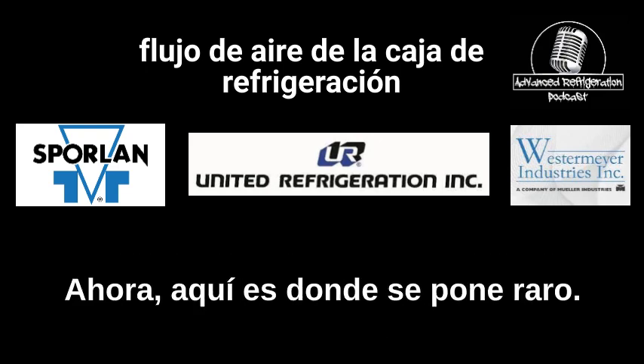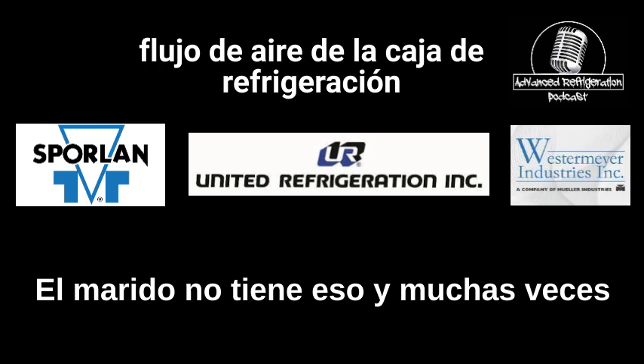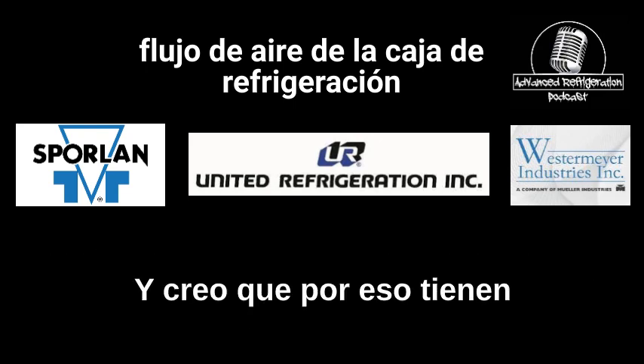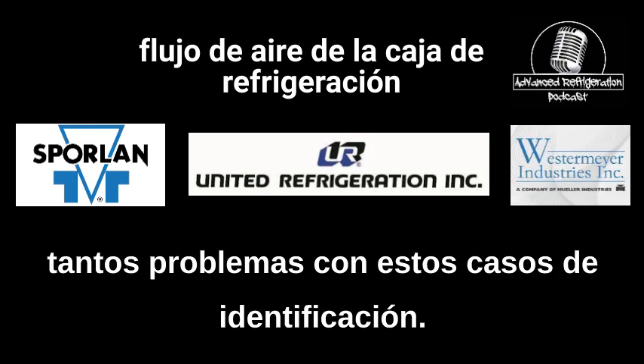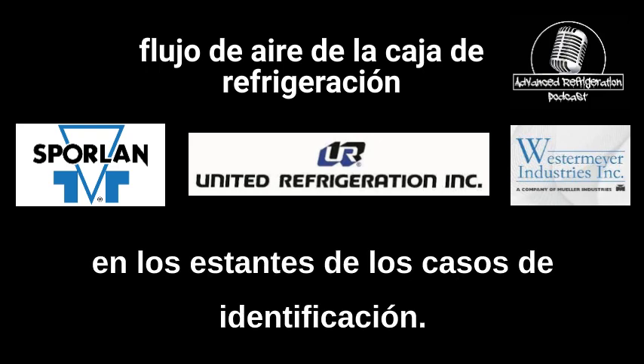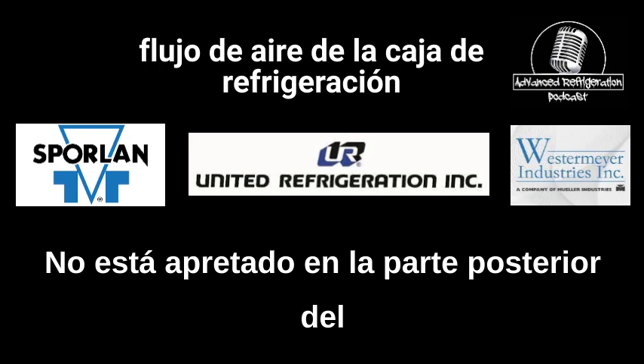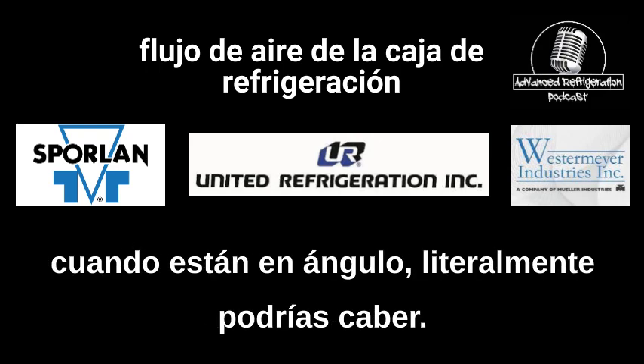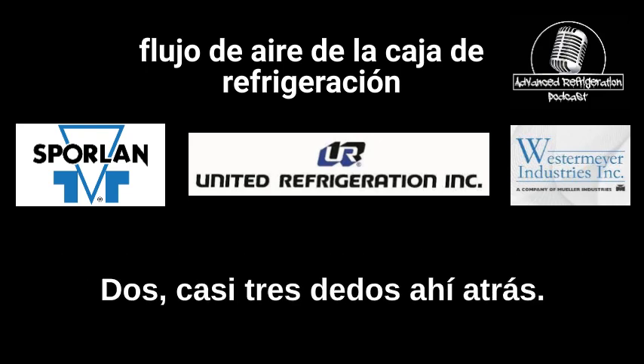Now, this is where it gets weird, though. Hussmann does not have that. A lot of times you could fit 2 fingers behind the back wall. And I think that's why they have so many issues with these Hussmann cases icing up now, because there is no backer on the shelves. It's not tight to the back even when they're straight. But when they're angled, you could literally fit two, almost 3 fingers back there.